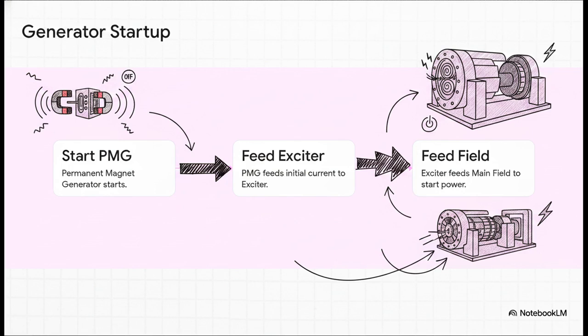Well, the answer is this elegant 3-step starting process. Step 1, we bring in a completely independent third element called a permanent magnet generator, or PMG for short. This is a much smaller generator sitting on the exact same shaft, but it has strong permanent magnets already built in, meaning it doesn't need external power to have a magnetic field.